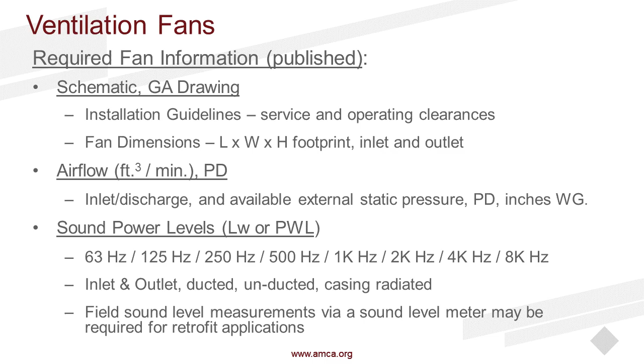Now, if you look at a ventilation fan, once again, get the data sheet, installation guidelines, length, width, height of the footprint, inlet and outlet dimensions, airflow, inlet, outlet, ducted, non-ducted or unducted, and casing radiated noise. Field sound levels, sometimes it's an old fan. It may be working at a completely different operating point than it was designed for, and that's how they got to operate it, because they don't want to buy a new fan.